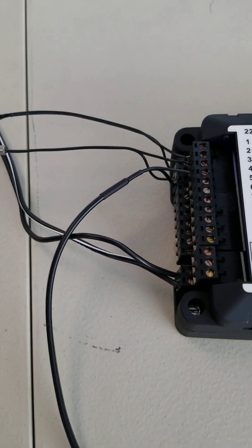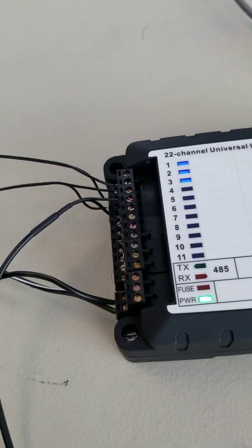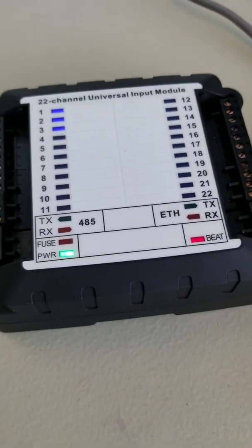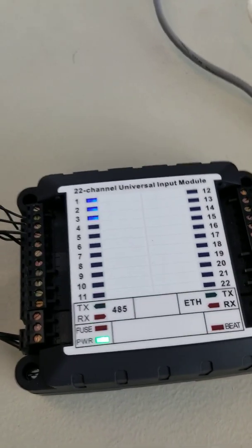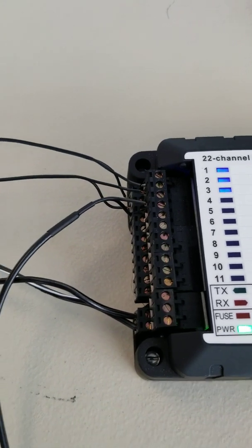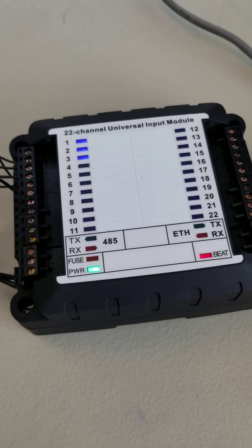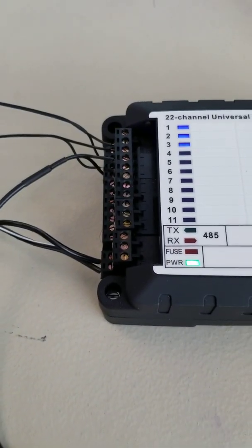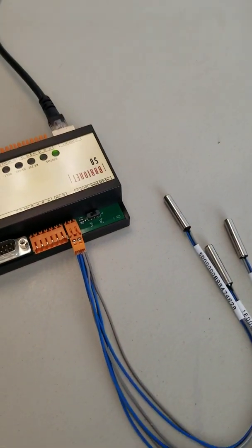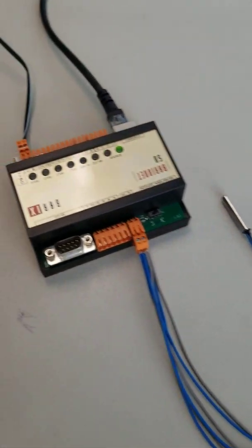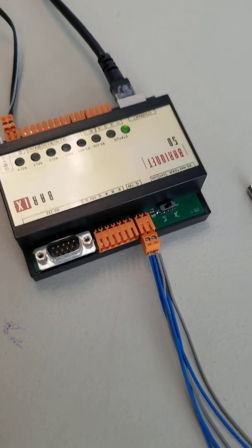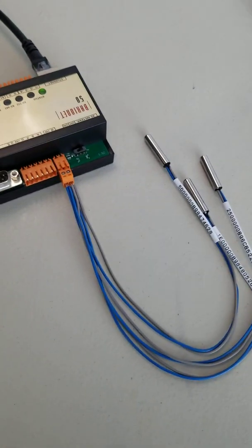And so in this scenario, if we wanted 30 or 40 temperature sensors in a space, we would need a couple of these high-density input modules. And each sensor would have to have a cable that goes all the way back to the input. And so then you can see that the cost starts to get pretty high if you have to do a lot of sensors and they all have to be home run to their own analog input. Whereas with one wire, you can put all of those sensors to a single digital I/O pin on a single one wire master, and they can share the cable.